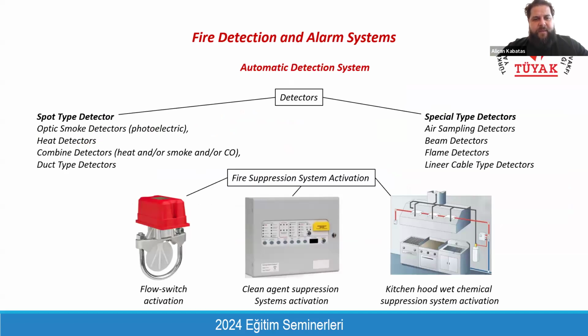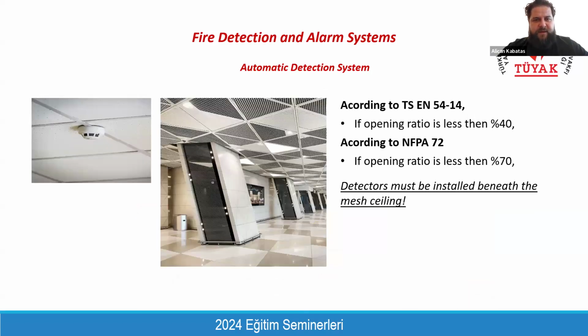And the main schematic of the fire alarm and detection system is that we will have some automatic detectors. And also we will have some alarm indication devices such as flow switches to understand if there is a flow, or we will have some kitchen hood system activation modules. Also, same for the clean agent. It means we are doing supervision for all of the fire suppression systems and fire detection systems, and we will be alerted in case of any activation or failure.